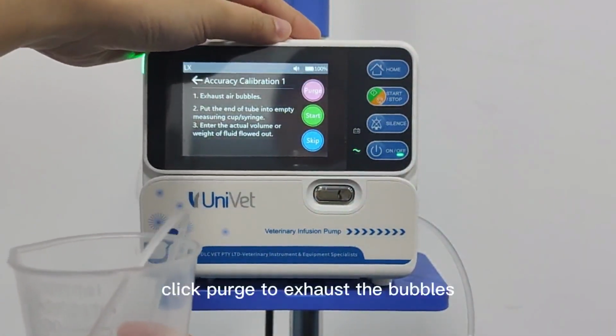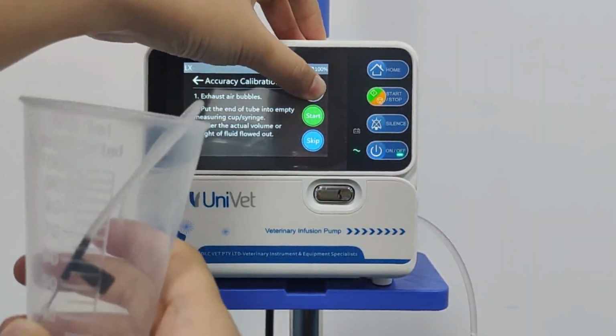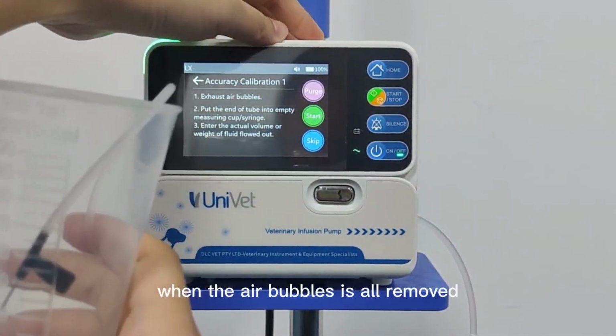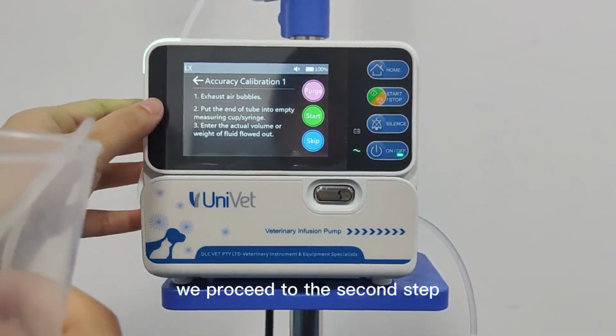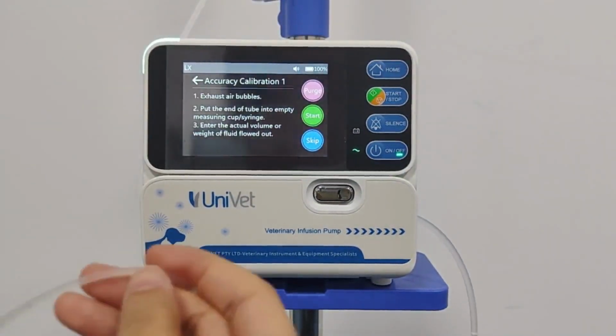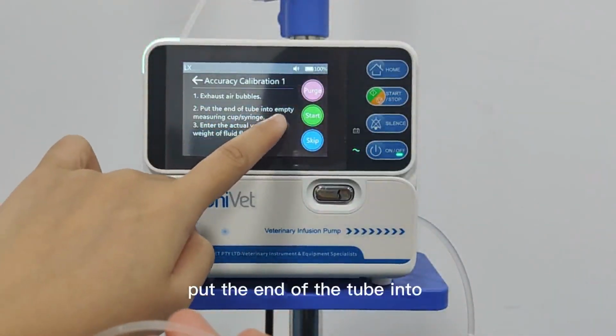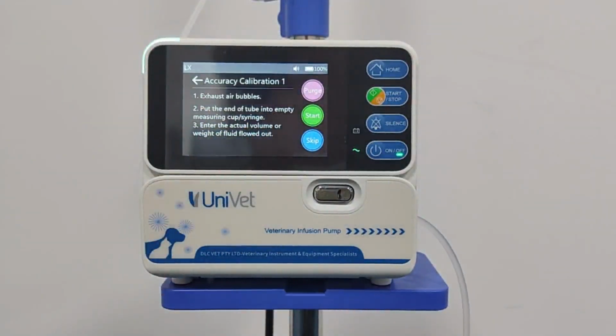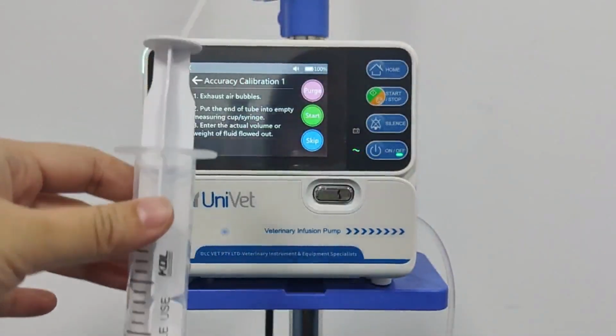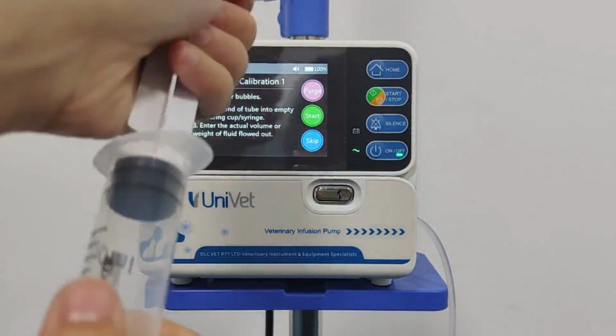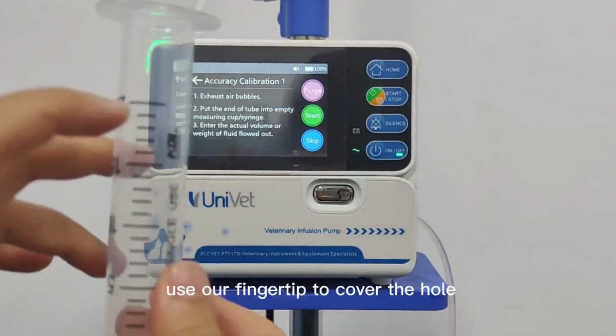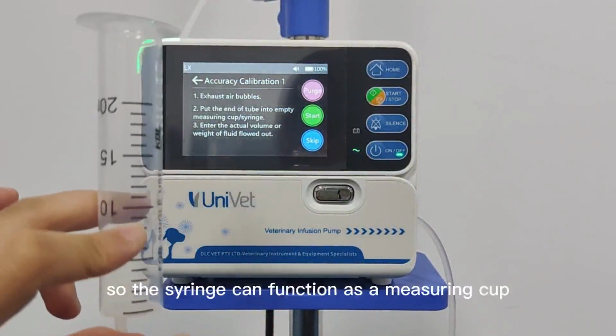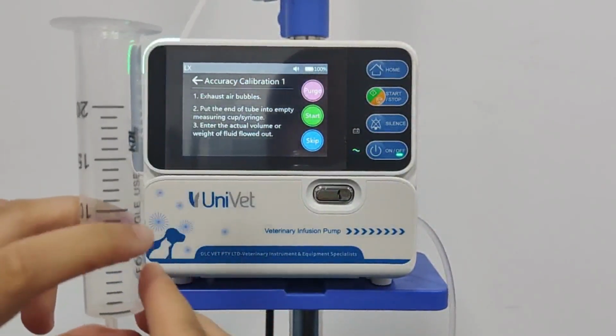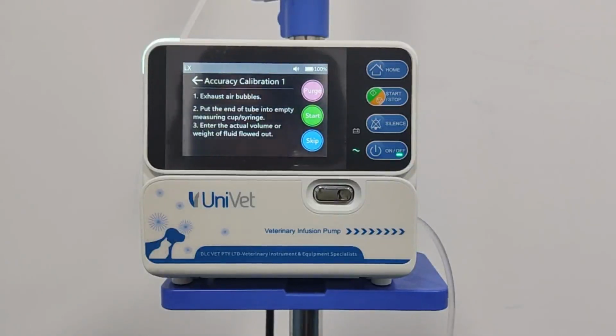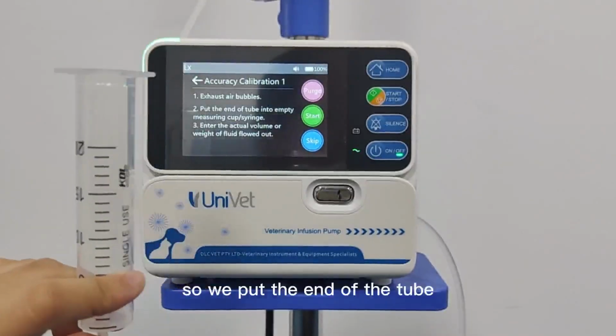Click Purge to exhaust the air bubbles. When the air bubbles are all removed, we proceed to the second step. Put the end of the tube into an empty measuring cup or syringe. Here is a syringe. We pull the plunger out. We use our fingertip to cover the hole, so the syringe can function as a measuring cup. So we put the end of the tube into an empty measuring syringe.